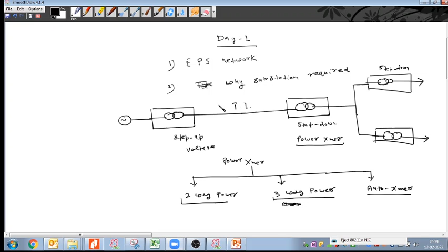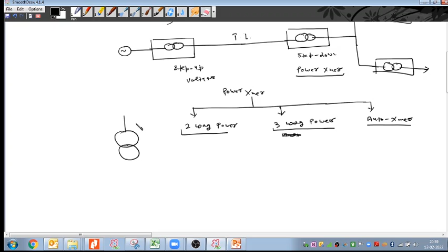Yes. So the point is that whenever we consider the HV voltage and LV voltage ratio, because we have the transformer, we have the high voltage side or primary voltage, and the secondary side or the LV voltage. So whenever the HV to LV voltage ratio is greater than 2, in that case we prefer to use a two winding type power transformer, and that is the reason every generating power plant has a two winding type power transformer, because they generate 11 kilovolts and then step up to 33 kilovolts, or 33 kilovolts is generated, then we step up to 132 kilovolts or 220 kilovolts. So the HV to LV ratio, suppose 33 by 11 kilovolts, this ratio is greater than 2, that is 3, right? It means it is greater than 2.